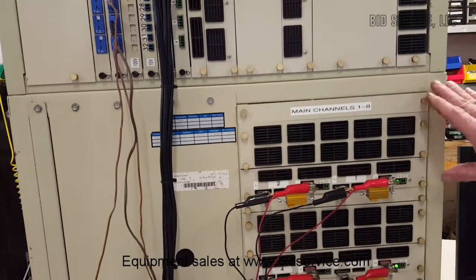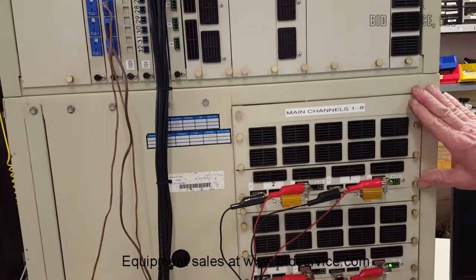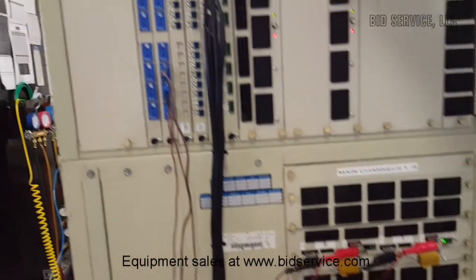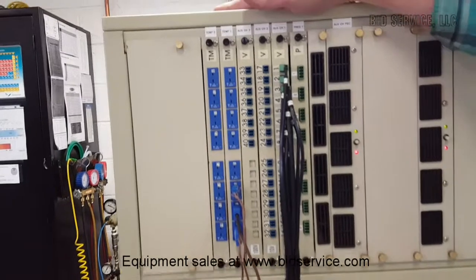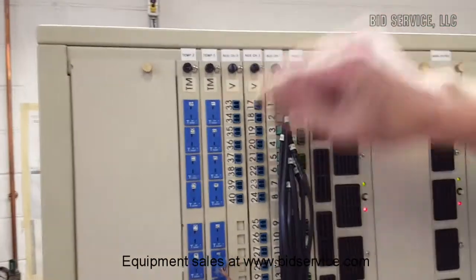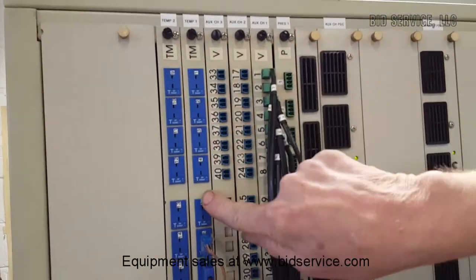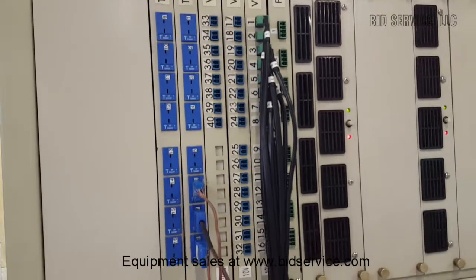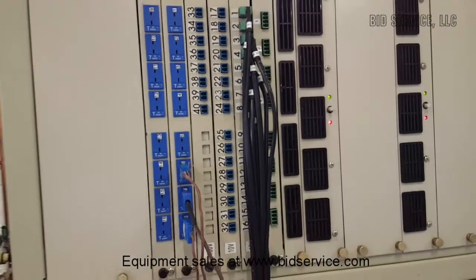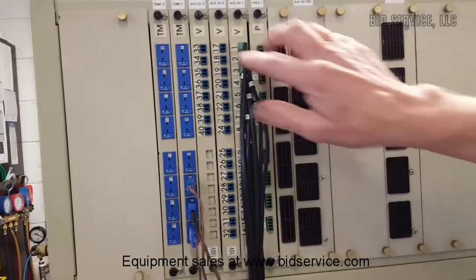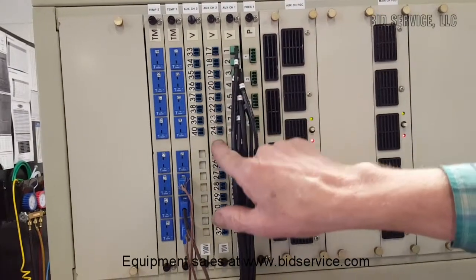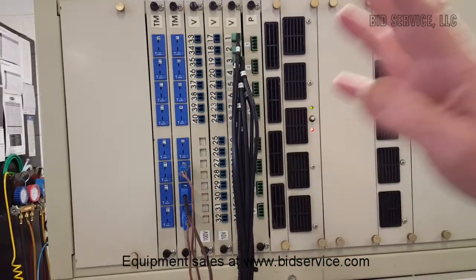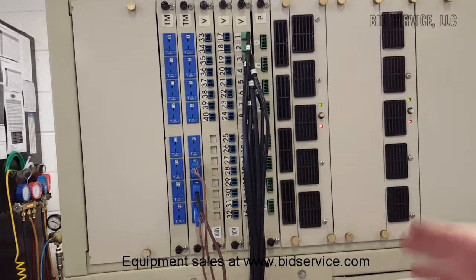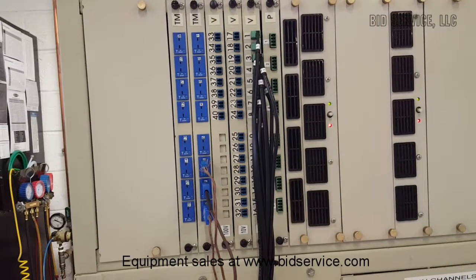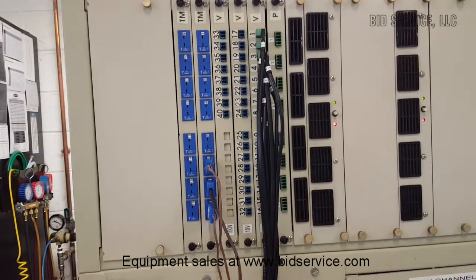Also, the system not only has the 8 main test channels, but let me explain these channels up here. These are all your auxiliary channels. You have 16 temperature channels where you can hook up a T thermocouple and measure temperature. You have 40 auxiliary voltage channels. These strictly are for measurement. They measure your device, they tell you how much voltage is going through that.